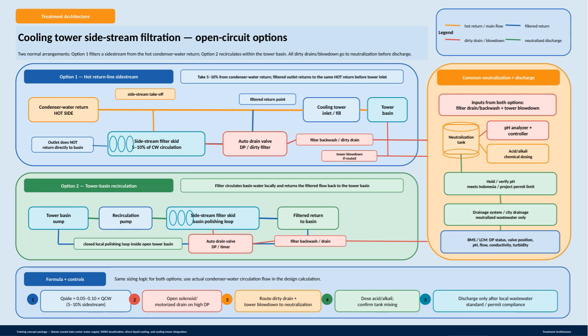From an operational perspective, the system includes automated controls, such as automatic drain valves triggered by differential pressure or timers, and a building management system that monitors parameters like differential pressure, valve positions, pH levels, flow rates, conductivity, and turbidity to maintain optimal performance. Finally, the sizing for these options uses the actual condenser water circulation flow, applying a logic of filtering between 5 and 10% of this flow in the side stream filter skid. The combination of precise filtration, chemical dosing, and monitoring ensures the water system runs efficiently while complying with environmental regulations.